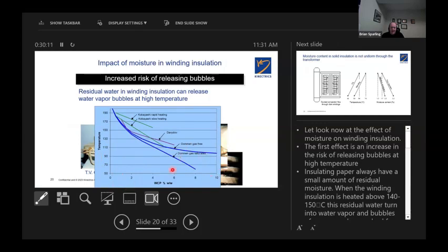So Oommen's curve, when bubbling is predicted, is a function of temperature, the hotspot temperature, and the water content in paper when the point in time has come when the moisture has stopped moving. So if we're at 0.5%, we're way down here when a transformer is new, this curve says they should be able to load it up to 190 degrees C hotspot temporarily before bubbles form. But in normal operation, we would never expect to go above 110, overloading maybe to 130.